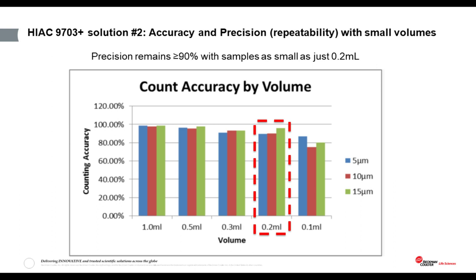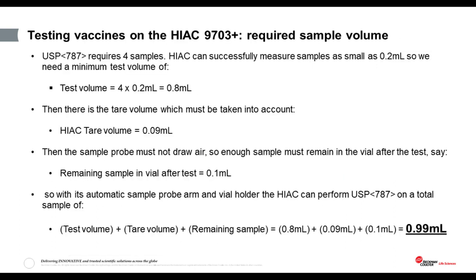So the counting accuracy itself can be demonstrated using certified reference beads. And you can see here from these test results that the HIAC demonstrates greater than 90% counting accuracy on samples containing reference beads in just a 0.2 milliliter sample volume.